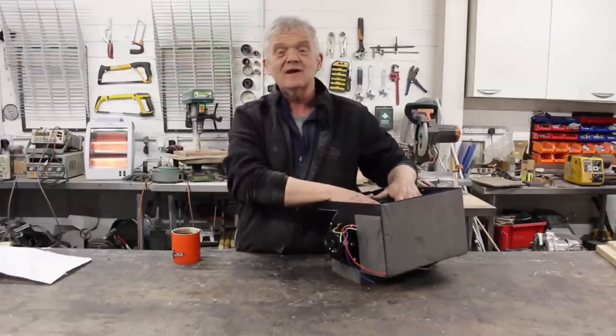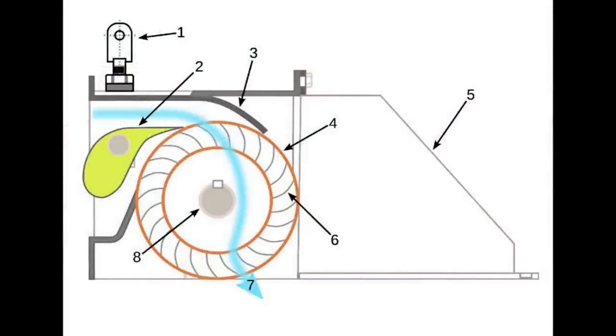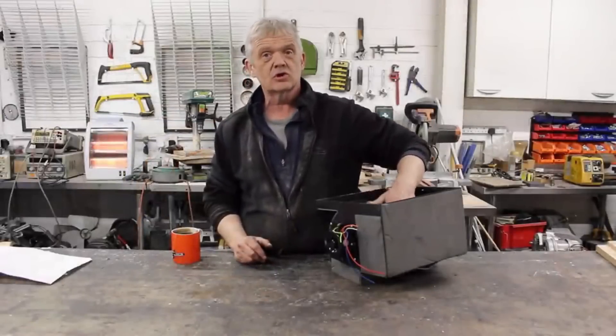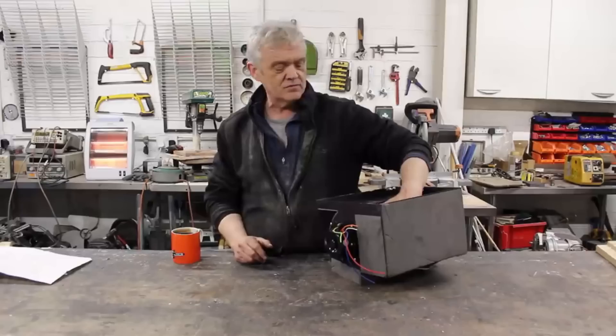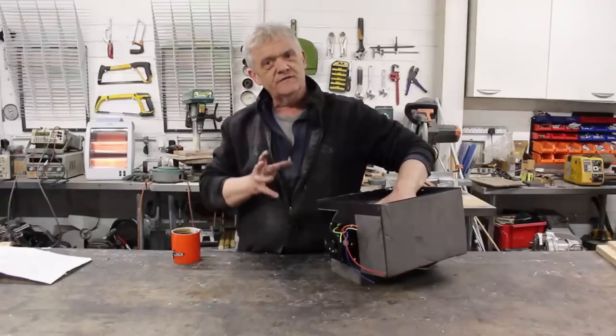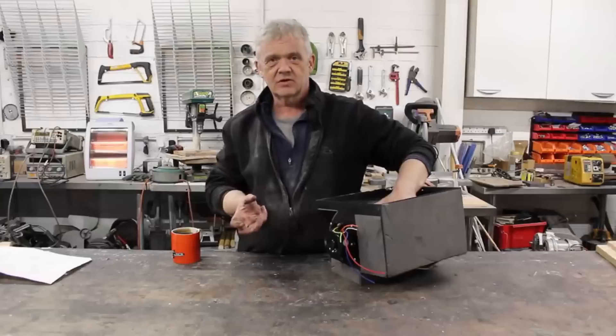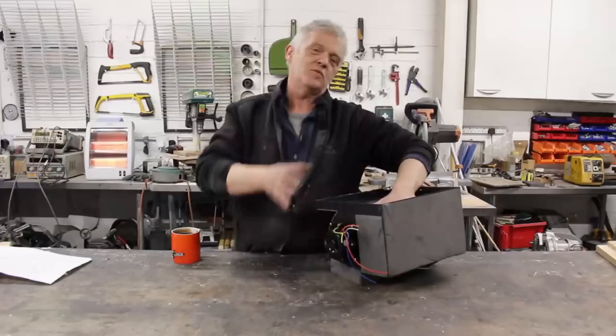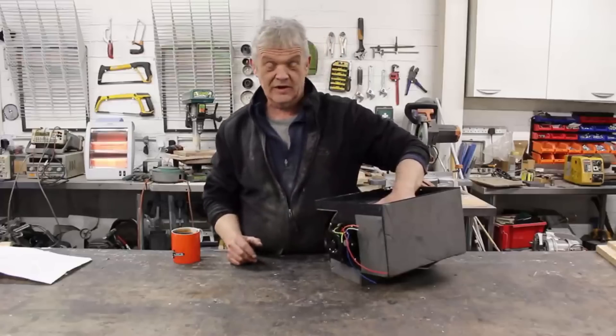Apparently it is self-cleaning because of the way the water flow goes — it flows in and instead of going around, it goes through to the other side, which can help with the cleaning process. In operation, its maintenance cost is very much lower than other turbine types, so it is well suited to micro-generation and low maintenance. Its peak load efficiency is less than something like a Pelton wheel, but its average efficiency is surprisingly good because it's able to cope with variable load.